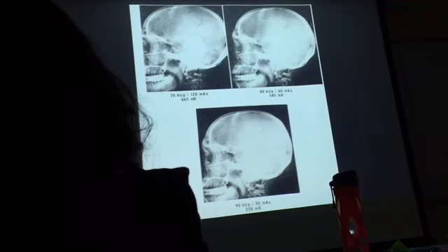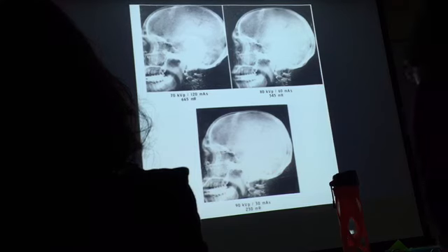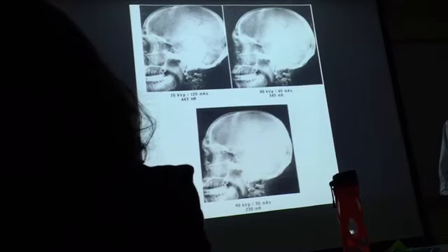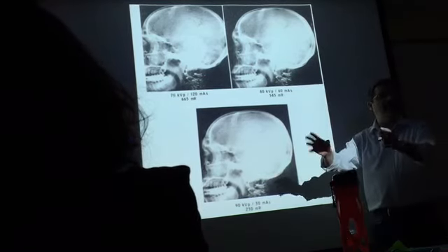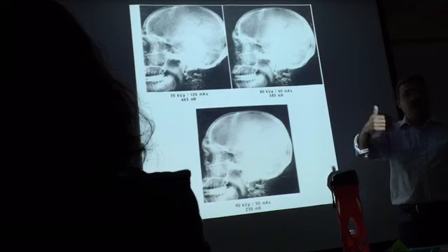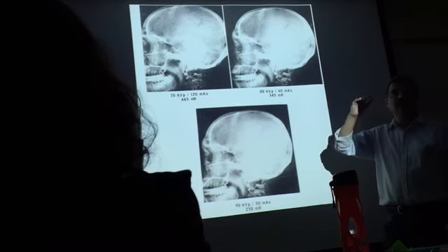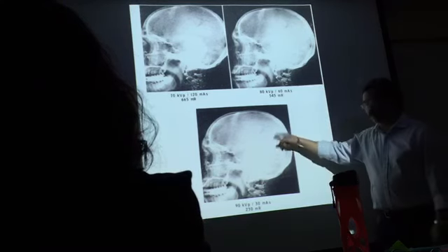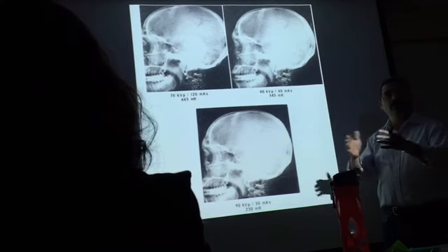Ultimately, that's the question you need to ask the radiologist. What do you want? Images that look like this, where it'll be easier to identify pathologies and anatomy, or something like this? It's a little more difficult, but look at the patient dose reduction. So it's up to them. The advantage with digital systems is that you can manipulate the image. And that's why, going back to what Maureen said before about techs tending to go higher on kVp, you reduce patient dose, but you have more ability to manipulate the image.